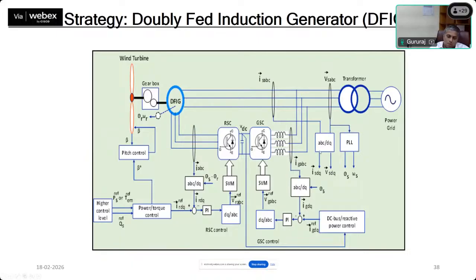I hope you're familiar with inverter controls. We go for ABC to DQ transformation because the PI controller works well with a DC signal that's compared and fed to it. Converting AC signals to DC signals this way, after the ABC to DQ transformation, you decouple them into D control and Q control: D control handles active power and Q control handles reactive power.